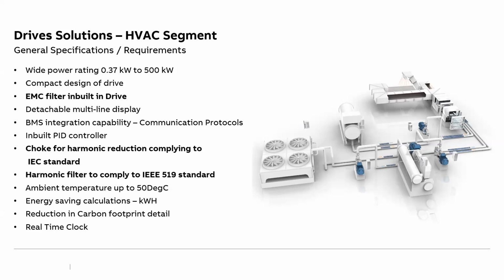So scheduling is one function, and the second function is the time stamping of errors. In many places, it is required that if any error has occurred or if any alarm was raised, it should be with proper time and date stamping. If there is a real-time clock, then we can have proper time and date stamping of all the errors, alarms, or if any VFD has tripped at any time. So this was about the selection criteria or major technical points which need to be taken care of. Apart from this, there are many other technical specification points. However, these are the major selection criteria.